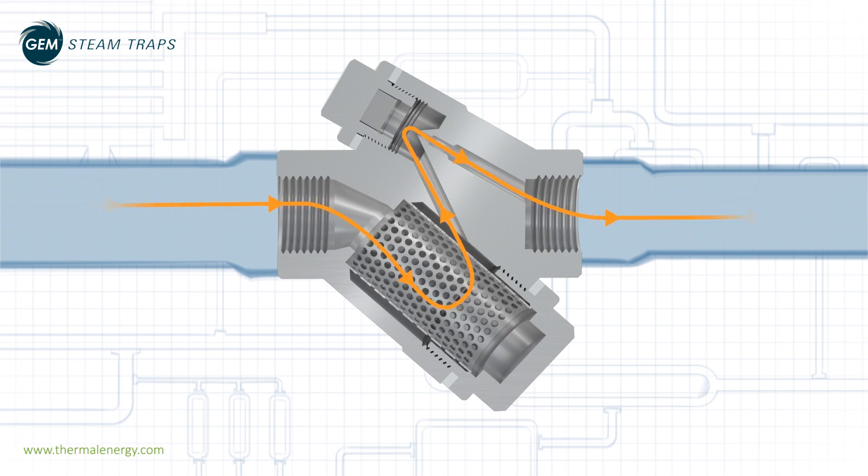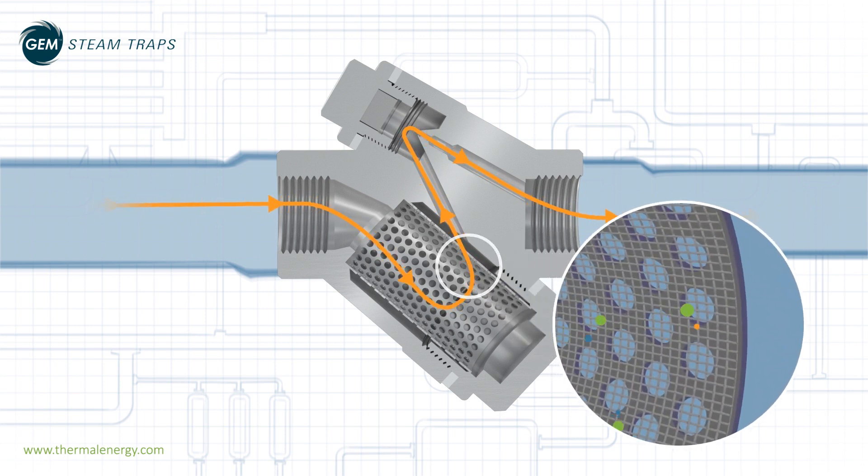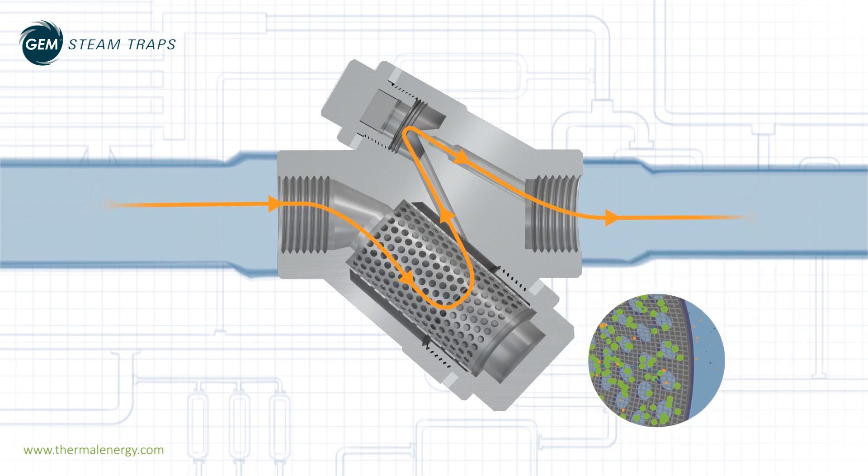To minimize service requirements, our GEM traps include a specially developed multi-stage filtration system. Within a GEM trap, the reinforced stainless steel mesh strainer basket is the primary means of removing debris. The strainer basket has a large surface area and a mesh size finer than the trap orifice. This optimal mesh size is designed to prevent blockage-causing debris reaching the orifice, while extending the intervals between cleaning.